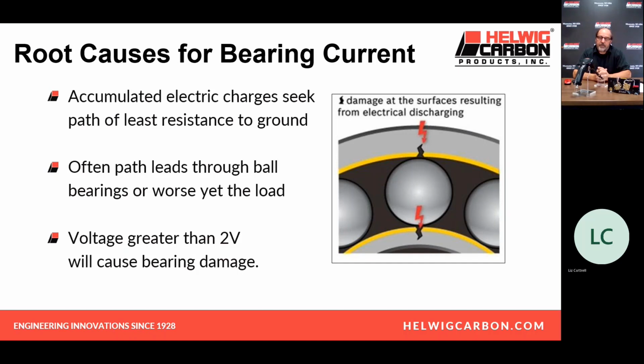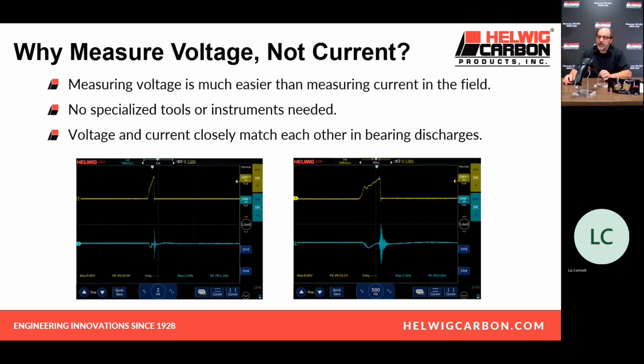If we see a voltage greater than 2 volts, it is damaging your bearing. There's no question about that. We have the motor lab here at Helwig. We've done extensive testing, really around 1.6, 1.7 volts. The discharge is enough to cause damage. We're conservative here, so we say if you're up to 2 volts, you are seeing bearing damage. Remember, you cannot measure this with your voltmeter. We'll get into that a little more later.